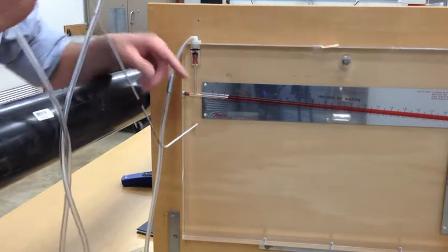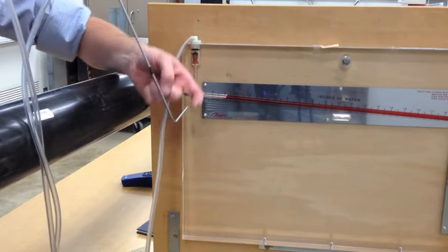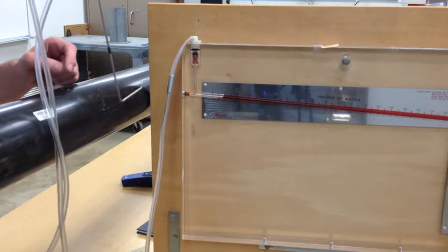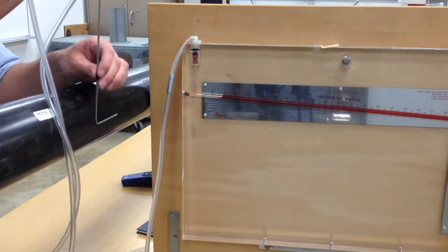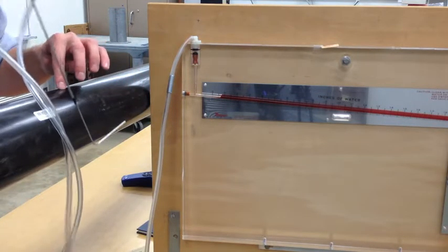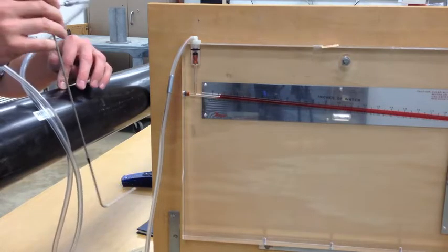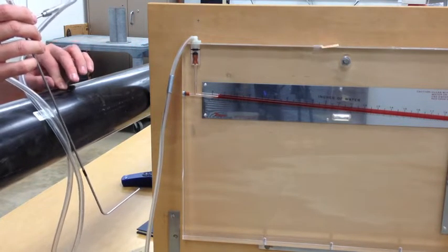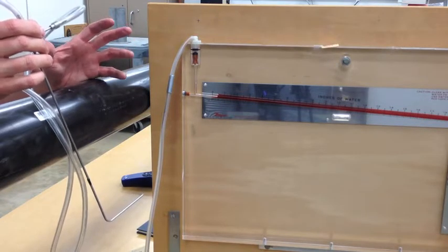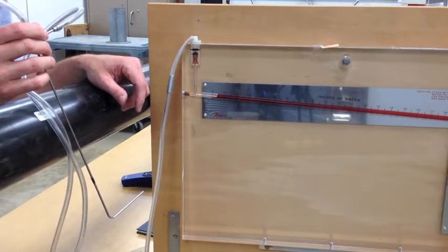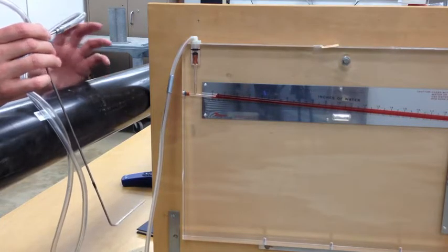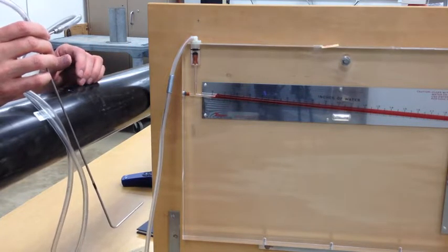Note also that the pitot tube has to be facing the direction of the airflow for it to go straight into there. So you put it in straight. I also put it in exactly halfway at the midpoint. We took a center line measurement. If we were just measuring velocity, remember that the center line is going to be a little bit higher than the average because the air flows fastest in the middle of the duct. So you'd multiply that by 0.93, and that should give you about what the average velocity would be.